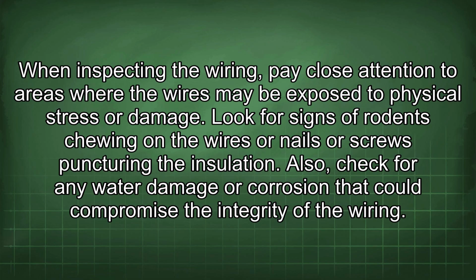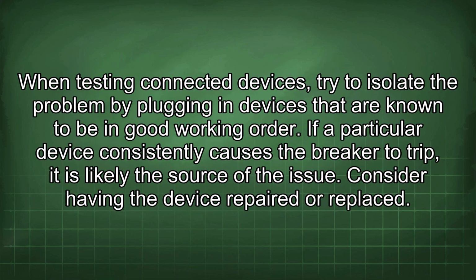When inspecting the wiring, pay close attention to areas where the wires may be exposed to physical stress or damage. Look for signs of rodents chewing on the wires or nails or screws puncturing the insulation. Also, check for any water damage or corrosion that could compromise the integrity of the wiring. When testing connected devices, try to isolate the problem by plugging in devices that are known to be in good working order. If a particular device consistently causes the breaker to trip, it is likely the source of the issue. Consider having the device repaired or replaced.